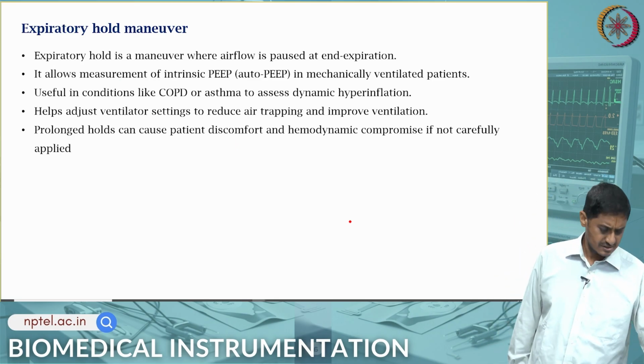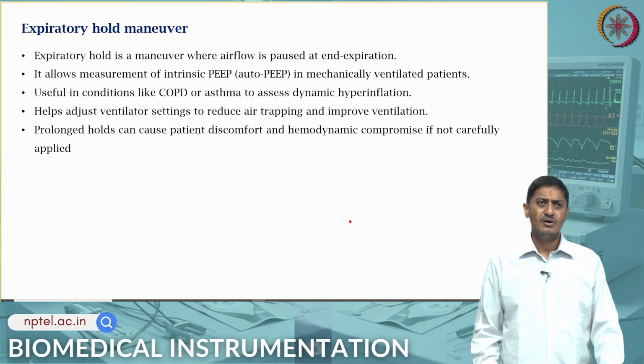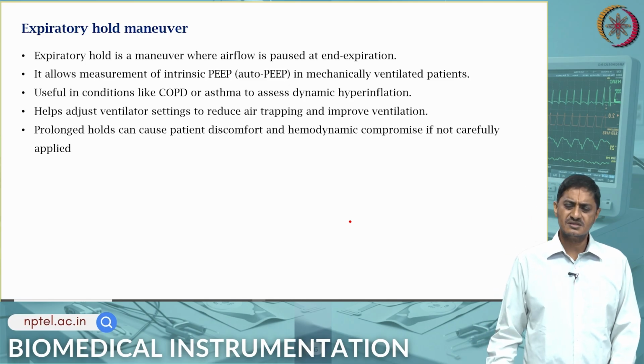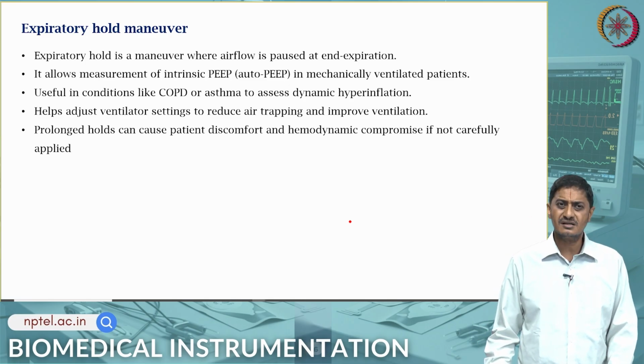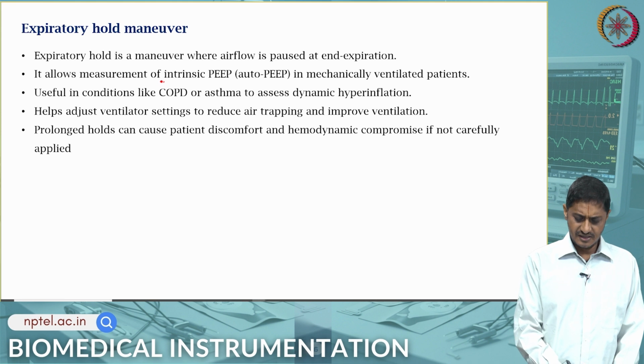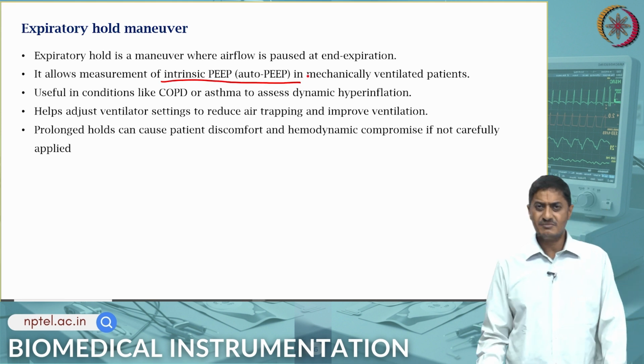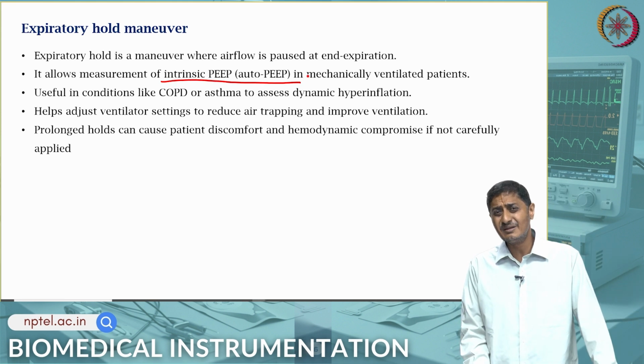The next is the expiratory hold maneuver. This is a maneuver in which airflow is paused at the end of expiration. It helps us to measure intrinsic PEEP or auto PEEP in mechanically ventilated patients, and how much the patient can exhale by themselves.